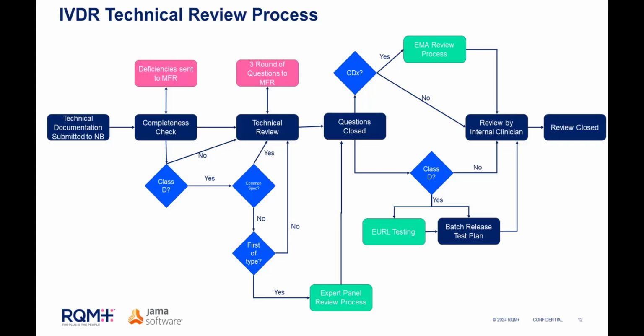After all the questions are closed, then it will be reviewed by an internal clinician. This is a new step in IVDR that didn't exist before. They're going to just review the performance evaluation mostly, and the clinical performance, and make sure that everything looks acceptable. And then the review will be closed. If you have a companion diagnostic, after the review is complete and all of the questions are closed, only then will the CDX process start. So that's the specific EMA review that's required. So if you have a CDX, keep in mind that that will extend the timeline quite a bit.